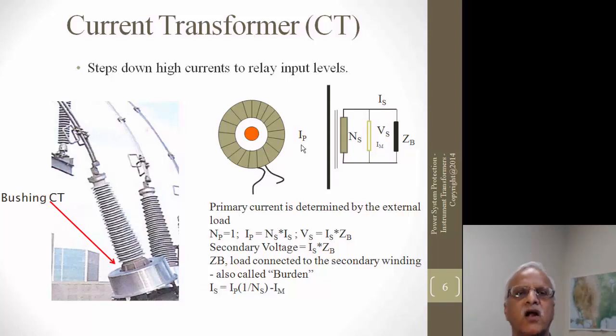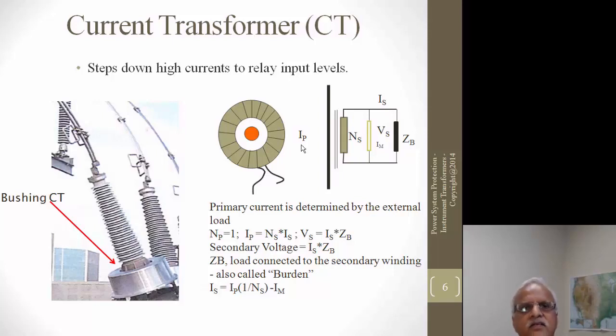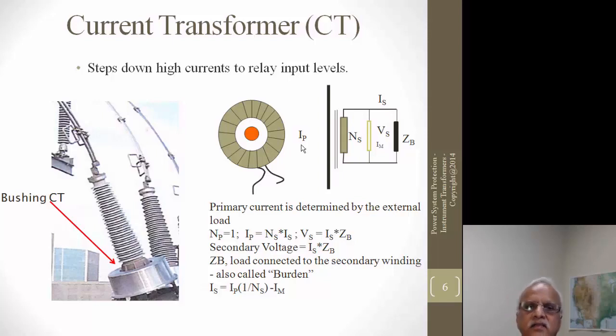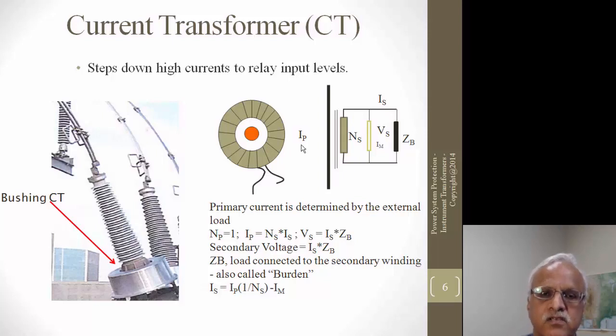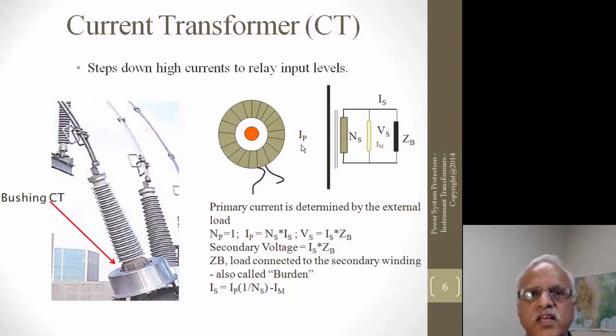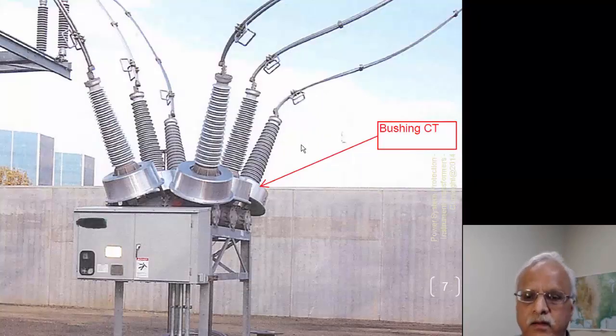If you short the secondary of a CT, it just balances the ampere turns and no voltage develops — it provides a path for secondary current to flow. If you open-circuit it, the primary current keeps flowing and the CT tries to push current through an open circuit, producing very high voltages on the secondary side. The CT saturates and gets damaged. So: on a voltage transformer you cannot short the secondary; on a current transformer you cannot leave it open.